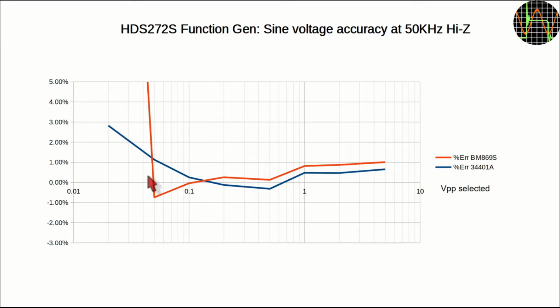That is because the BM869S, in line with most true RMS meters, needs a minimum voltage to give accurate readings. In this case, the stated accuracy is only valid if the signal is at least 10% of the range. If it is between 5 to 10%, an additional error applies, and below that, all bets are off. The most sensitive range is 500 millivolts, so 10% is 50 millivolts, 5% is 25 millivolts, but 0.02 volts peak to peak is just 7 millivolts RMS, so no wonder that the error goes off scale.